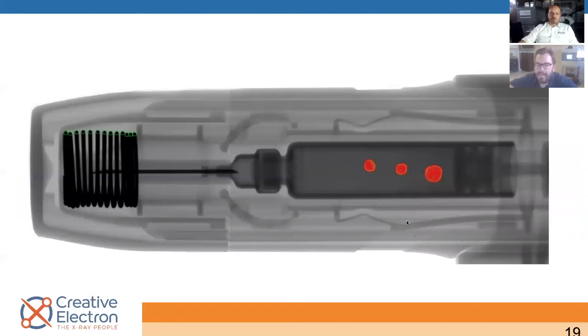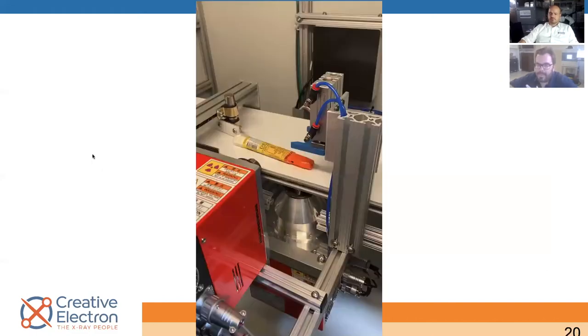Here's another example — this one doesn't have an empty vial, but it has some big bubbles inside. On the left side, our algorithm is counting how many coils a spring has. A coil count gives you the torque — the repeatable action. If one spring has 13 coils and the next has 12, it might not work the same way. For an EpiPen it's more of a gross action, but for some other devices you rely on the action being perfectly repeatable.